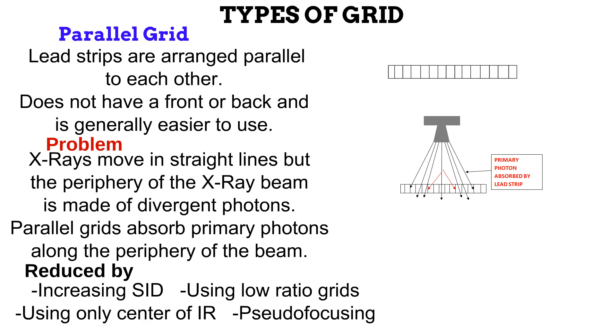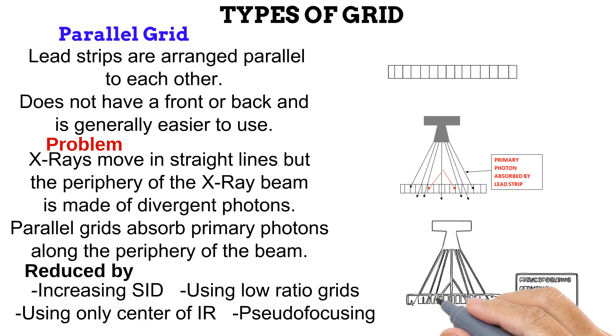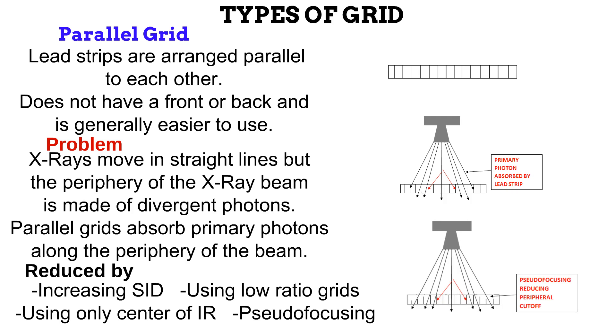Lastly, peripheral cutoff can be reduced by something known as pseudo-focusing. In this, the manufacturer reduces the height of the lead strips at the edges of the grid — the peripheral lead strips. As seen on the diagram, this makes it easier for the divergent peripheral photons to pass through.